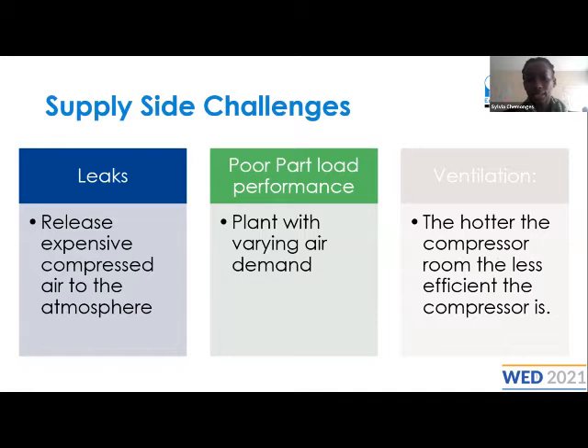So what are some of the challenges that we face on the supply side? One of the most common challenges, which is a major part in a compressed air system, is leaks. Some sections of the piping have maybe rusted over time. If you've owned a compressed air system for around 5 years, I'm sure there's around 25% of leaks within the system. So that's a big challenge.